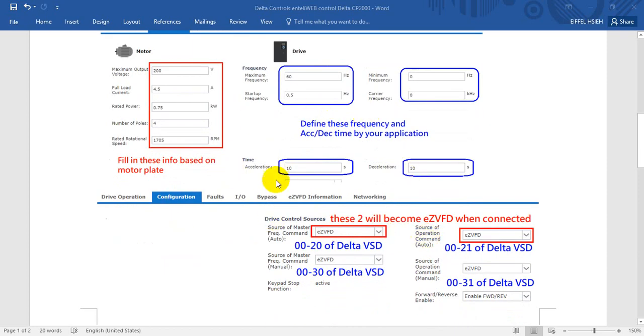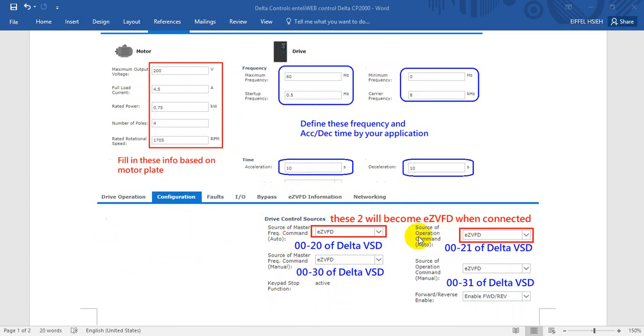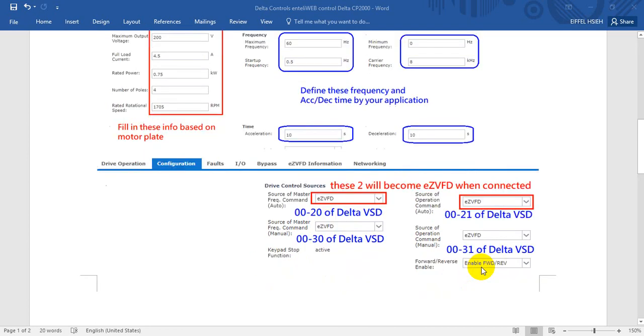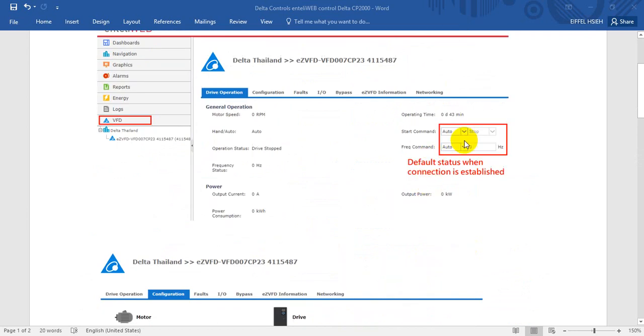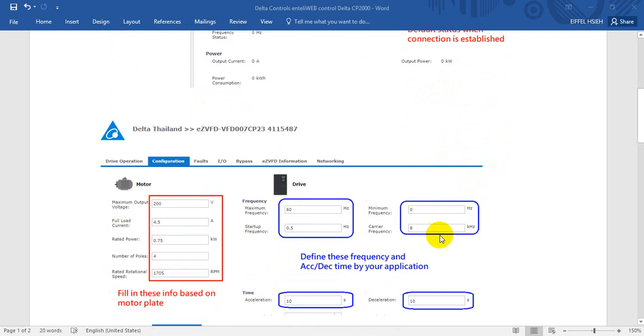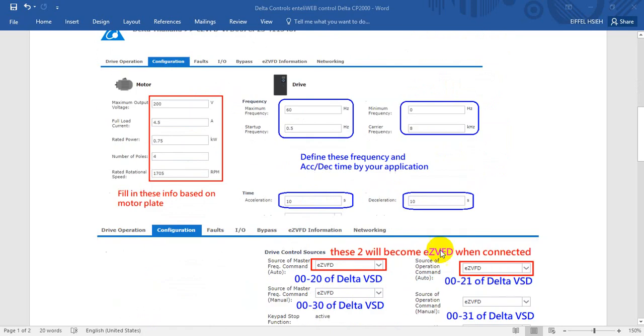We scroll down and you will find here we have the driver control source. The source of master frequency is in auto mode, and also the operation command is auto. This one is exactly the same as Delta VSD parameter 00-20 and 00-21. Here is for the manual setting, and later we will switch this one from auto to manual so we can do some basic setting and we can change the acceleration and deceleration time.